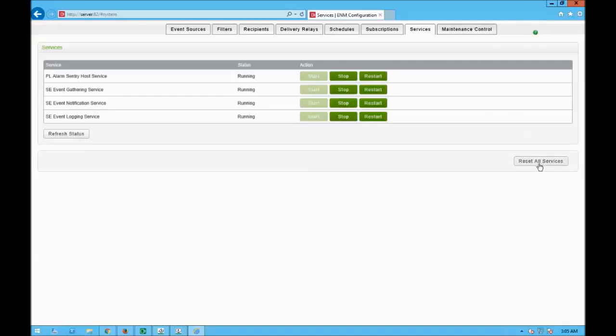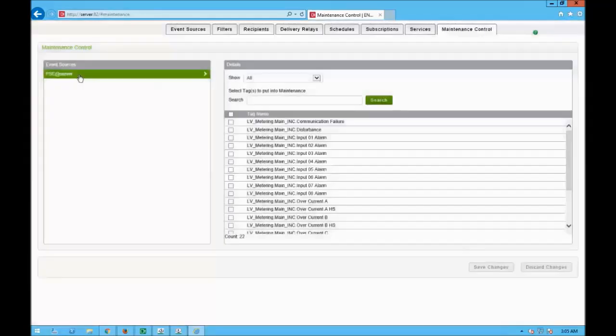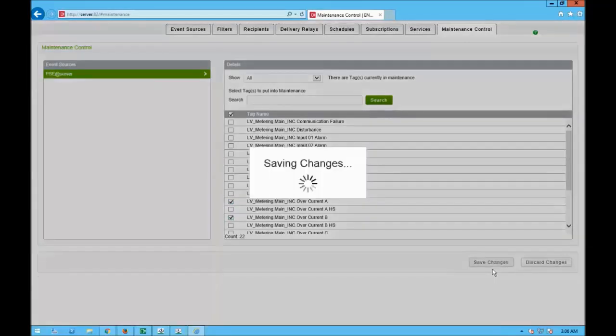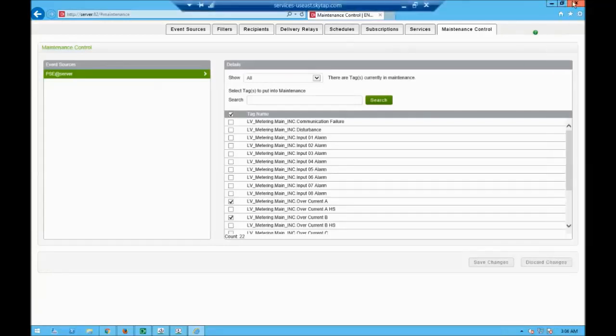I do a fresh restart for everything just to make sure it's all running fine. Then I click on maintenance control — my final tab. Here I can choose which tags to put in maintenance mode. For example, if I force a circuit breaker to close and need to do maintenance work, I don't want to receive SMS or emails for those tags. I select a few, click save, and whenever an alarm is linked to those tags I will not receive notifications. Once I'm done, I close the ENM configurator by clicking the X.